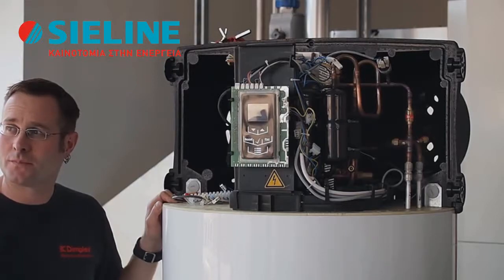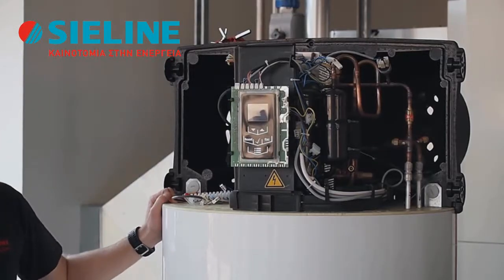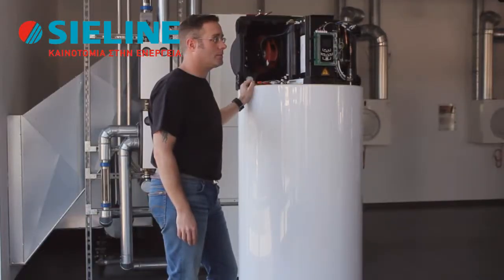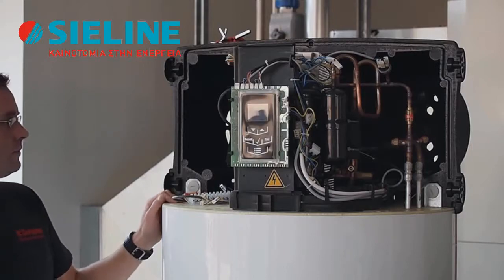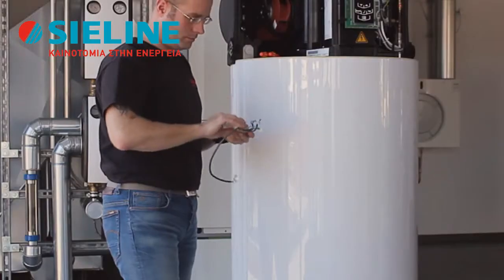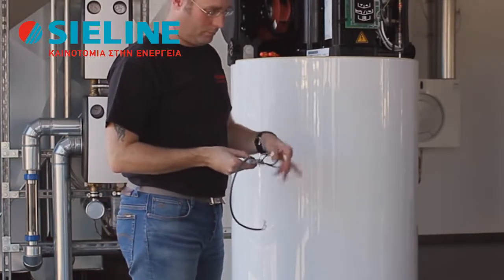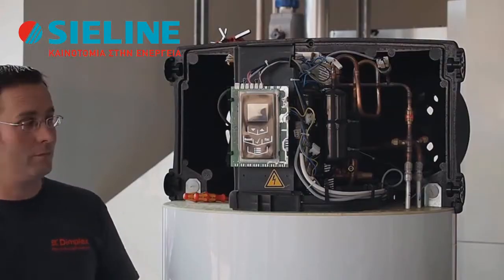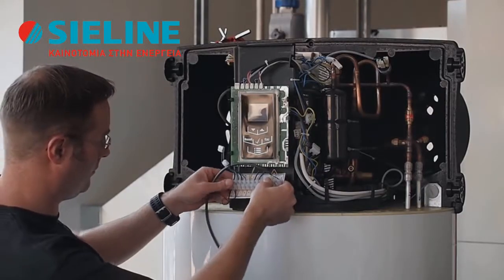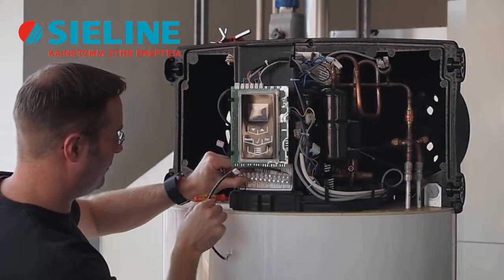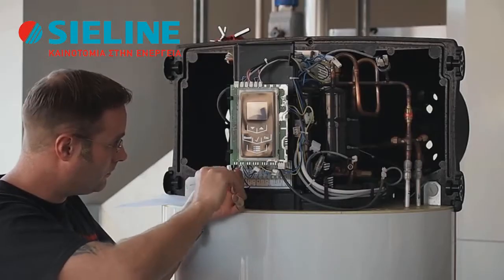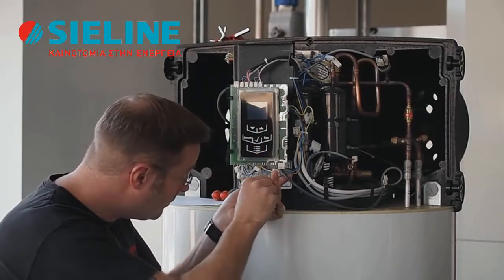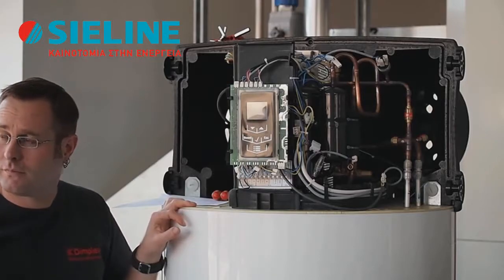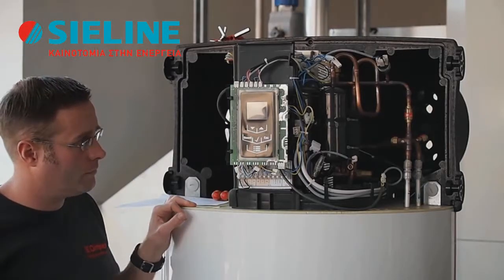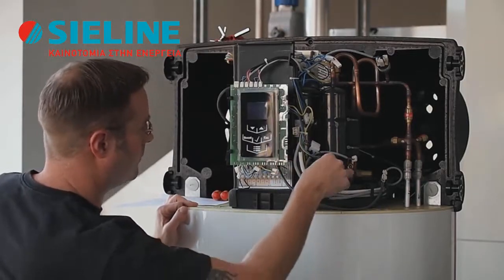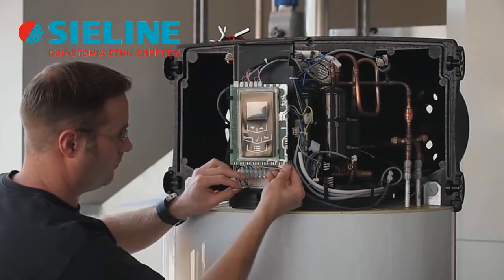If you want to make any further connections, like for example a solar thermal system or a photovoltaic system, you have to use the prefabricated terminal strip as shown. After fixing the terminal connection kit, you must now wire it in. To do this, you must loosen the X4 plug and plug in the new X4 plug from the terminal kit.